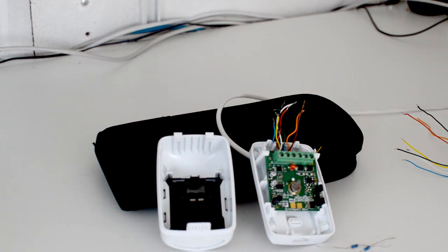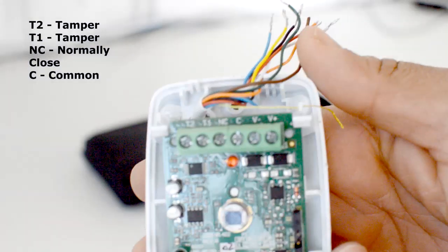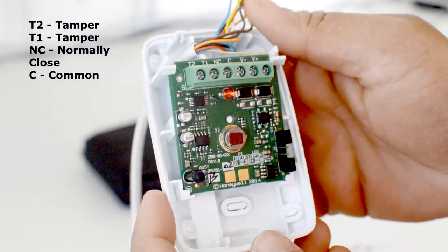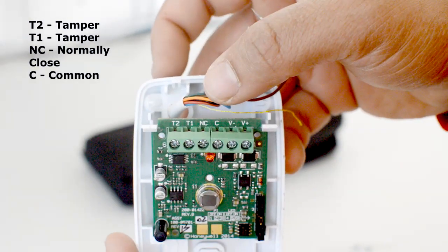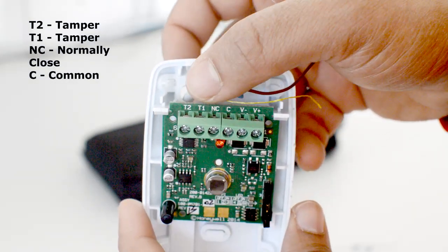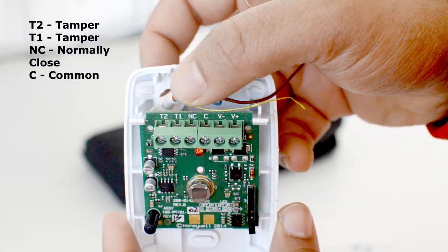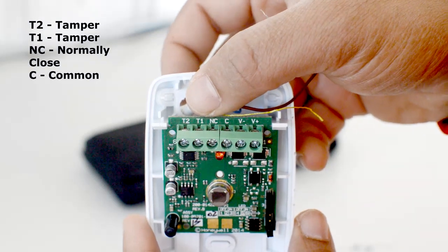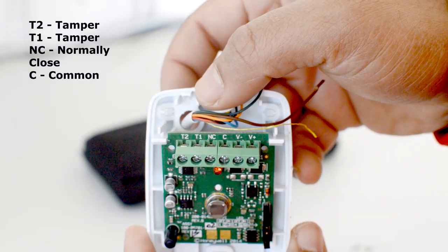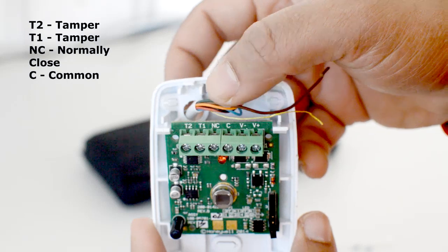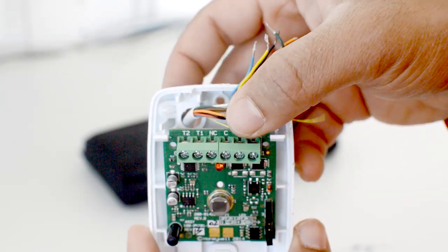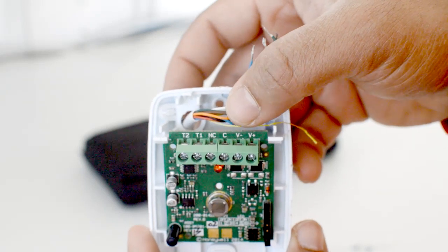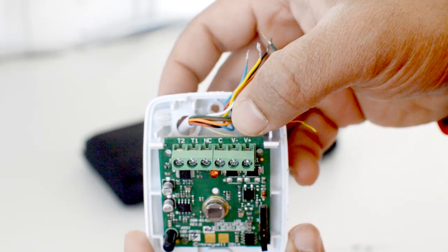Let's see how the wiring happens. First of all, you need to get familiar with the terminals. This is a grade 2 system. The first one is T2, which we call tamper, and T1. Then you have NC, normally closed. C is your common. Then you've got V minus and V plus, which is your voltage ground and then the positive.